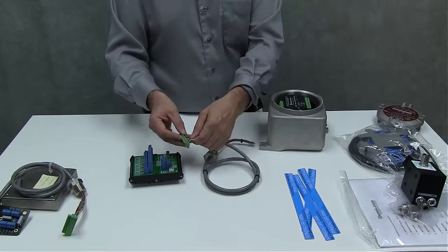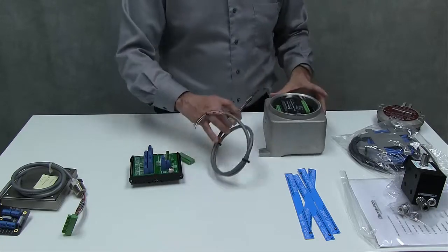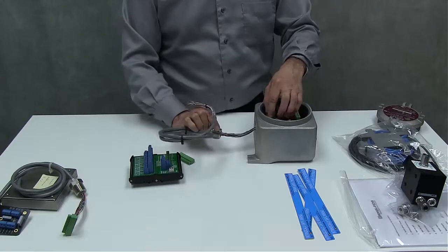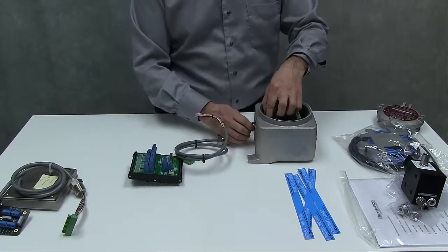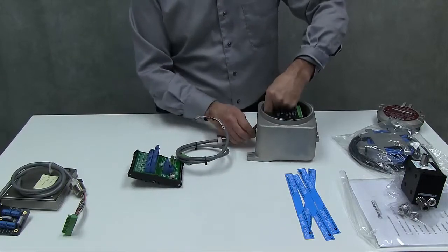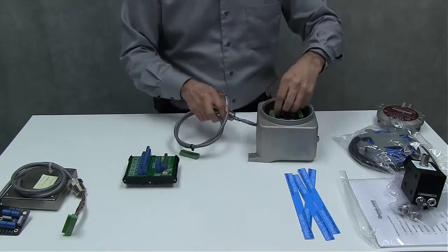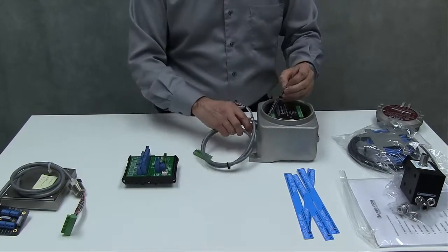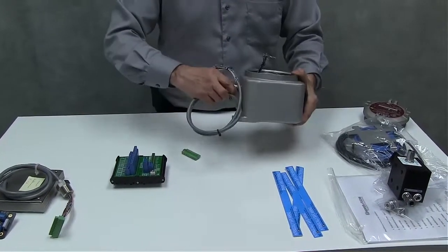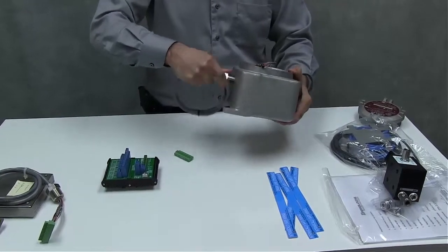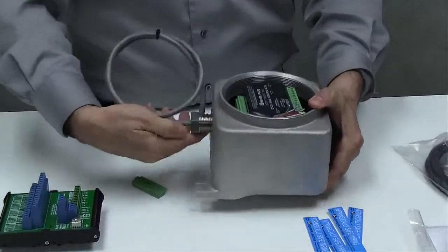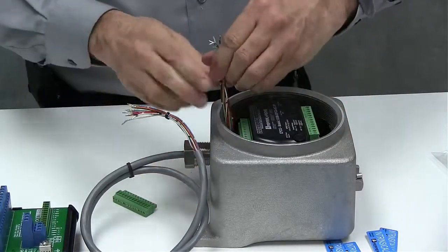So once this is terminated then you can screw this into the enclosure through this cable clamp. And so this would screw in here, you have to have at least five threads to maintain the explosion proof. So that would go in there.